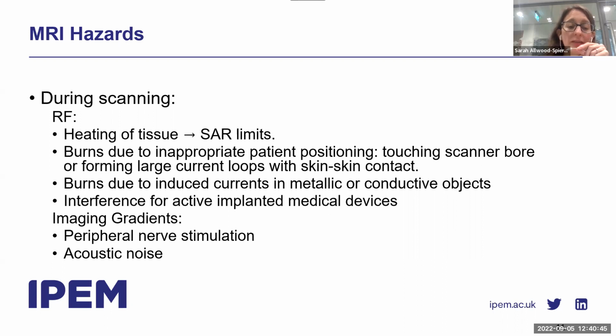We also have the issue of interference for active implanted medical devices. From the imaging gradients, subjects may experience peripheral nerve stimulation, and this switching of imaging gradients is what causes the noise of the MRI scanner. So anyone in the room during a scan must be protected from that acoustic noise, including the patient. Everyone must wear ear protection.